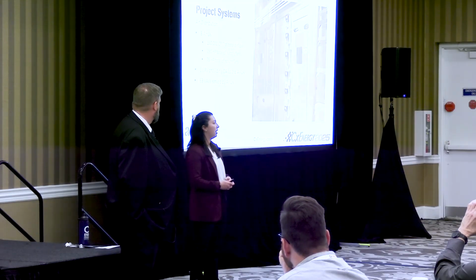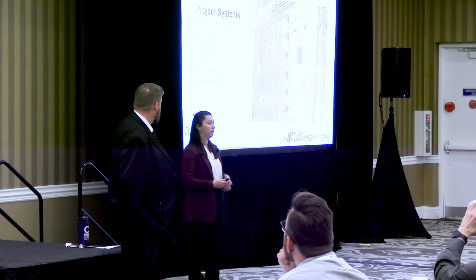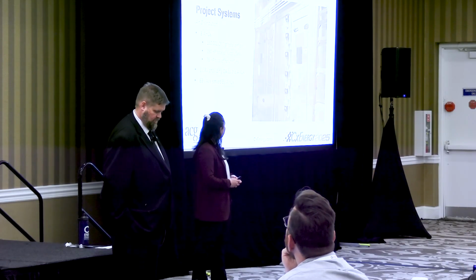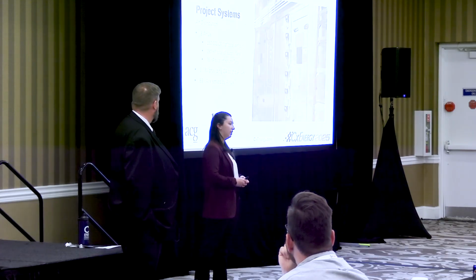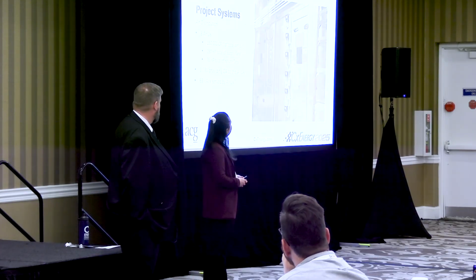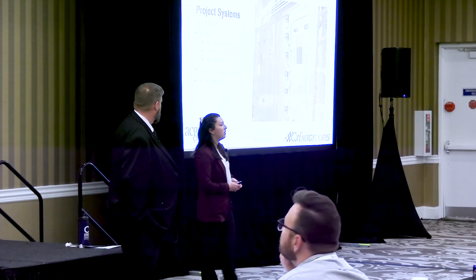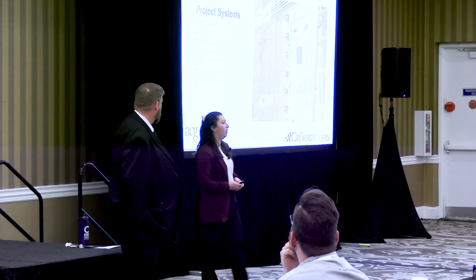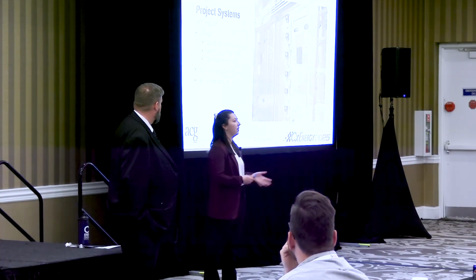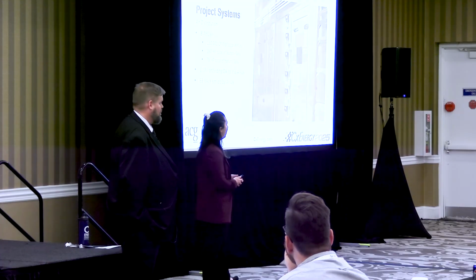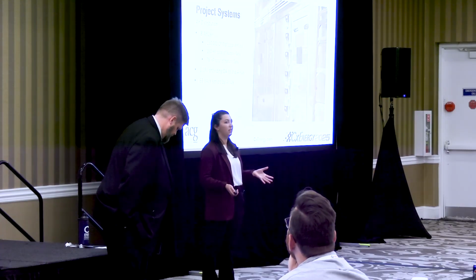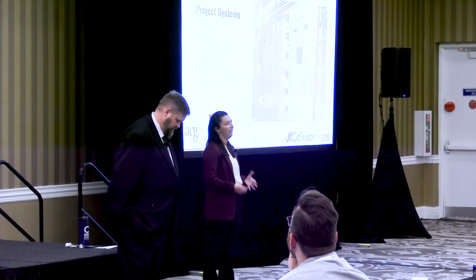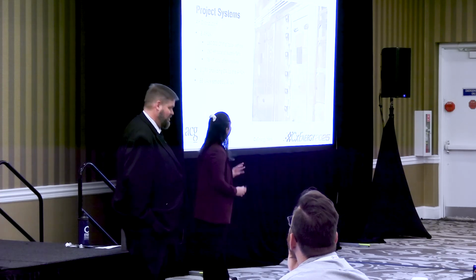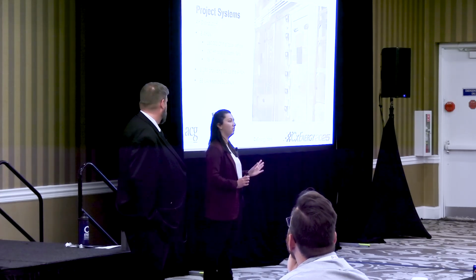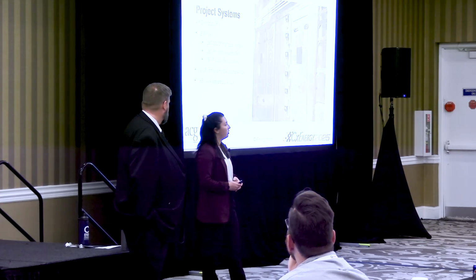Each of these air handlers has 4 supply fans and 4 return fans. One of the things that we found with commissioning this is that these variable speed fans were not rated for 60 hertz on the VFDs. They're actually rated much higher than that. And I know that a lot of times we think of 60 hertz as that limit, but in reality, that is imaginary. We can go above that, even if it feels weird, as long as the motors are not within that service factor.